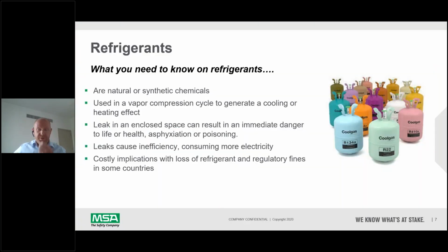So first, refrigerants. I'm sure everybody on this call is an HVAC expert, so you know that refrigerants can be either natural or synthetic chemicals. The natural ones are ammonia, propane, carbon dioxide, and water. And then the synthetic ones are manufactured to have unique cooling capacities at different pressures and temperatures. They're all used in a vapor compression cycle to generate either cooling or heating. A leak of these gases in an enclosed space can be dangerous because there's a risk of asphyxiation. When you're breathing in a refrigerant gas, you're not breathing in air, so this can cause suffocation. And some of the toxic gases, such as ammonia or R123, can be more dangerous.